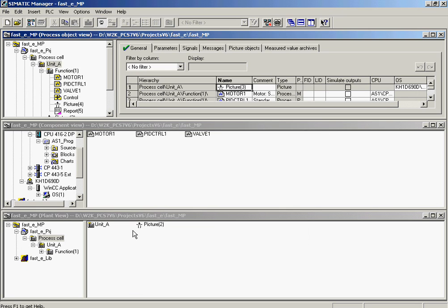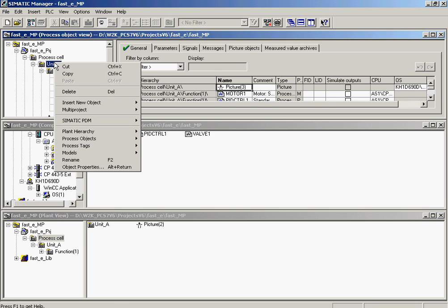With PCS7, it is possible to create a process graphic hierarchy in the OS for operator navigation which matches the plant hierarchy configured in the controller. The top level in the picture tree hierarchy must correspond to level 2 in the plant hierarchy.